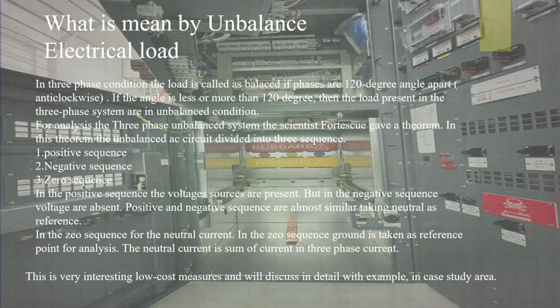What is meant by unbalanced electrical load in a hotel? In a three-phase condition, the load is called balanced if the phases are 120 degrees apart. If the angle is less or more than 120 degrees, then the load present in the three-phase system is in an unbalanced condition. For analysis of the three-phase unbalanced system, the scientist Fortescue gave a theorem. In this theorem, the unbalanced AC circuit is divided into three sequences: 1, positive sequence; 2, negative sequence; 3, zero sequence.